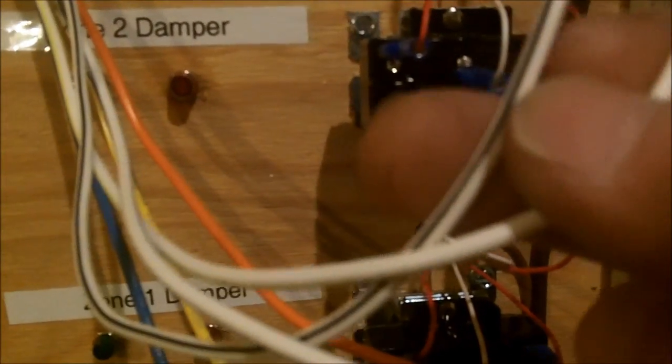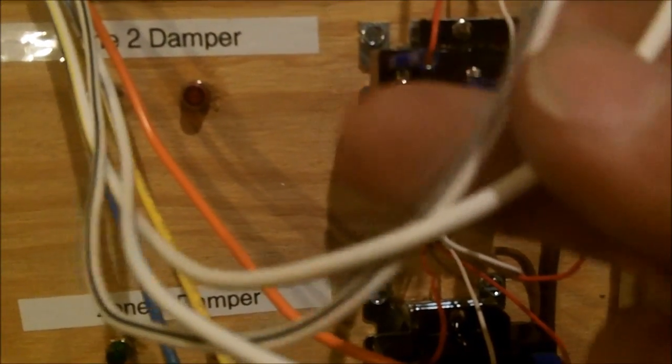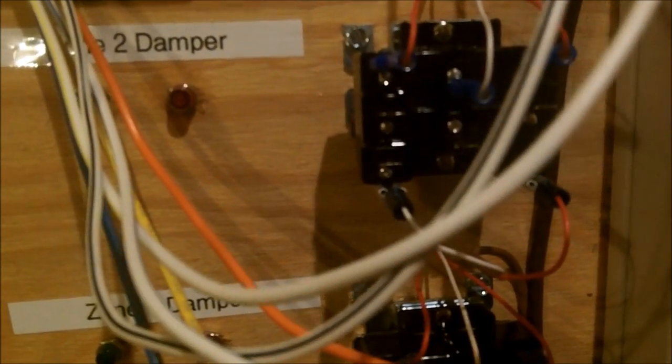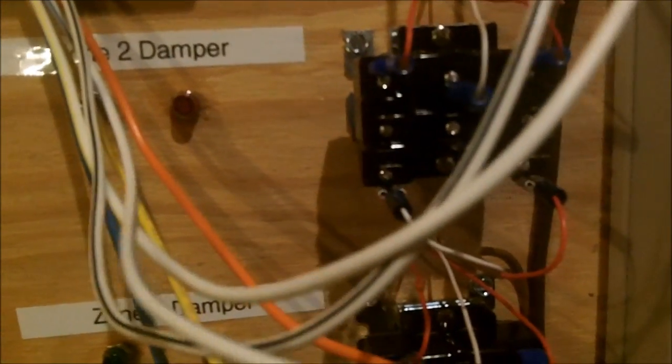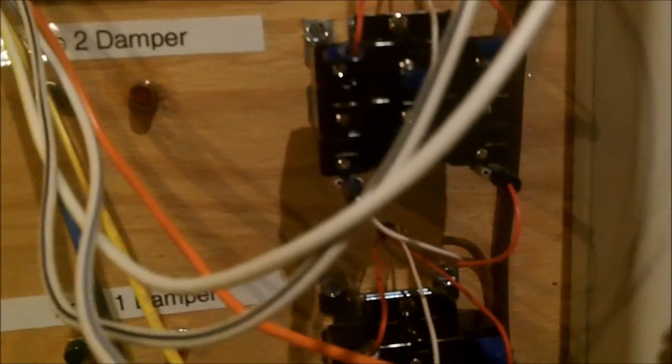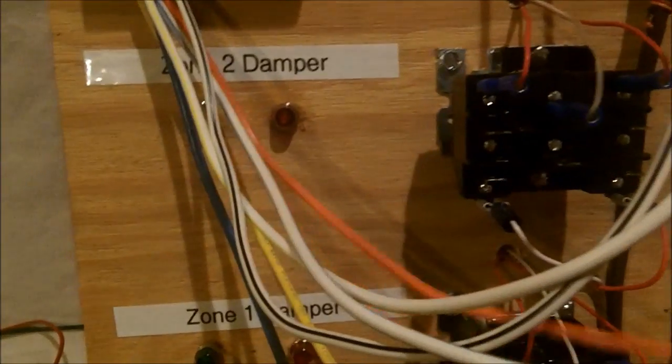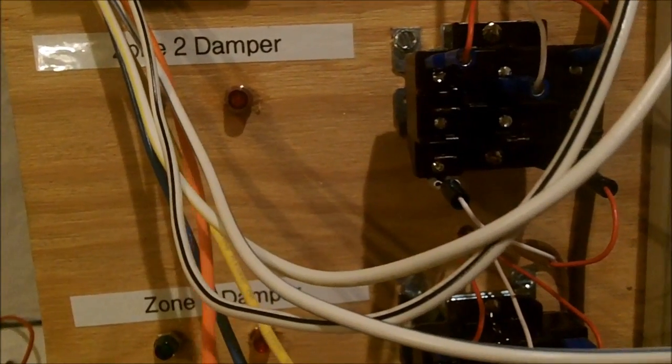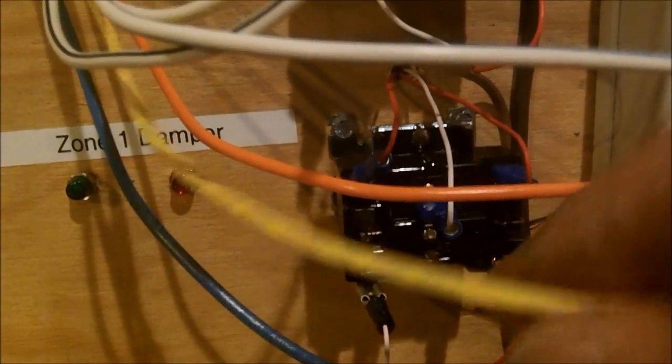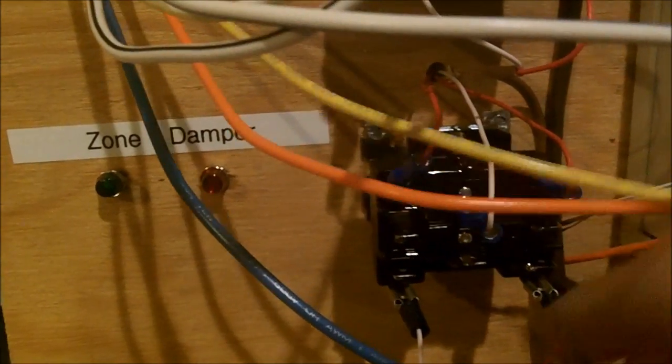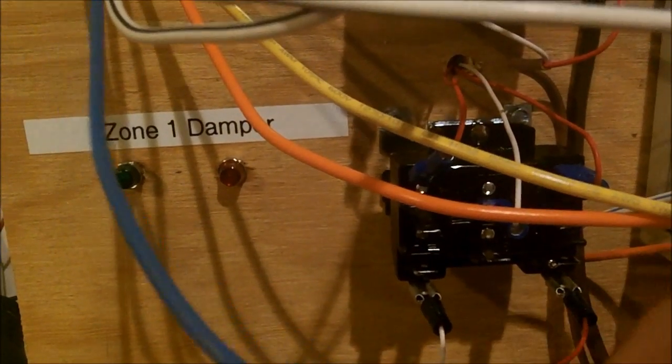Black and white being your 120 volt. Yellow and white is your common wire. And your blue and white is the 24 volt hot. Your orange wire is your normally open. Your yellow wire is your common. And your blue is your normally closed.